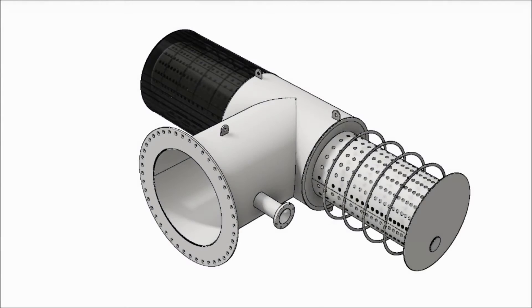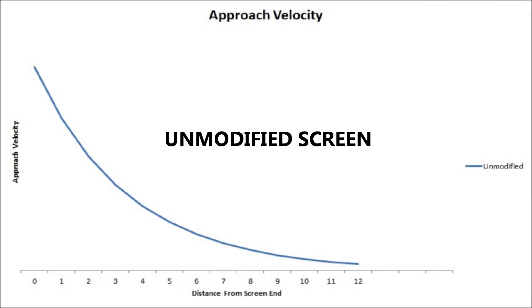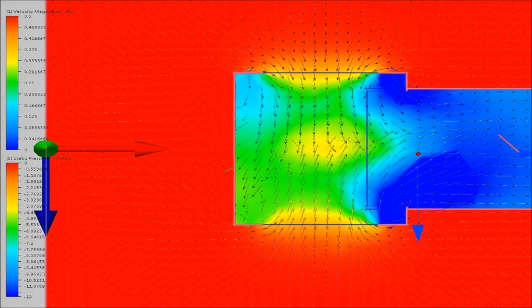The heart of our system is the Cook Legacy Flow Modifier. An unmodified screen may have peak local velocities ten times faster than the average. All flow goes through one small area, while most of the screen goes unused.